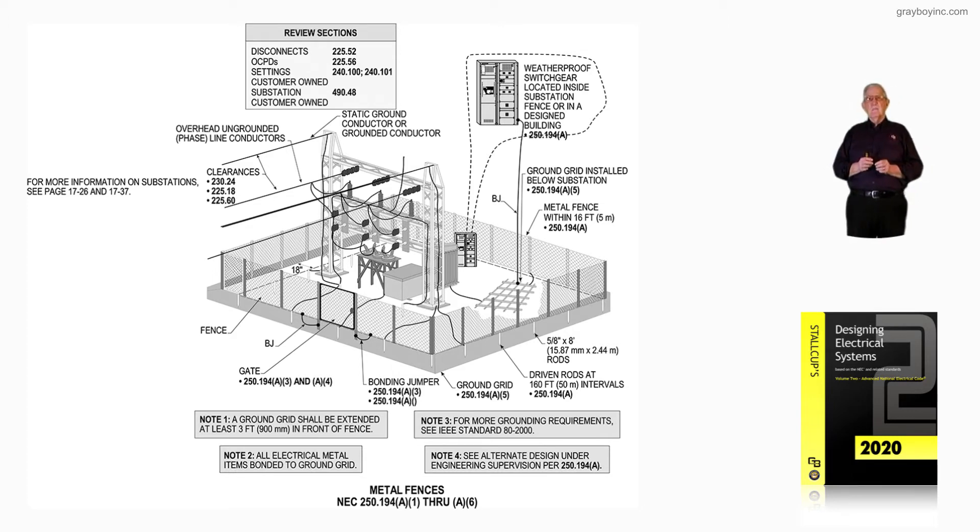The metal fence within 16 feet has to comply with 250.194A. You have your gate, and you've got to make sure that the gate is continuously bonded in accordance with 250.194A3 and A4.